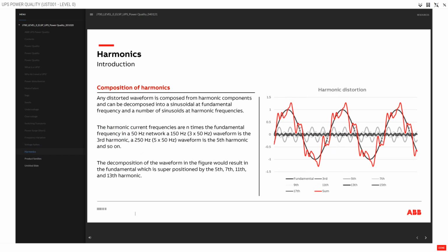Composition of harmonics. Any distorted waveform is composed from harmonic components and can be decomposed into a sinusoidal at fundamental frequency and a number of sinusoids at harmonic frequencies. The harmonic current frequencies are n times the fundamental frequency. In a 50 Hz network, a 150 Hz, 3 by 50 Hz, waveform is the third harmonic. A 250 Hz, 5 by 50 Hz, waveform is the fifth harmonic, and so on. The decomposition of the waveform in the figure would result in the fundamental, which is superpositioned by the 5th, 7th, 11th, and 13th harmonic.